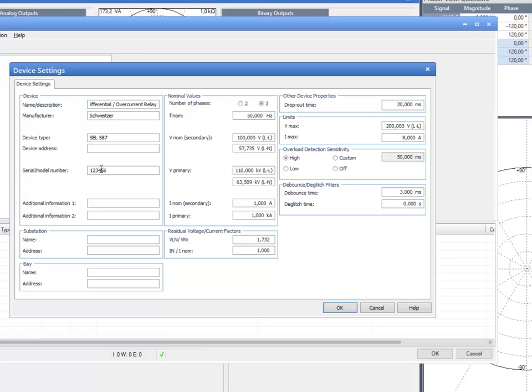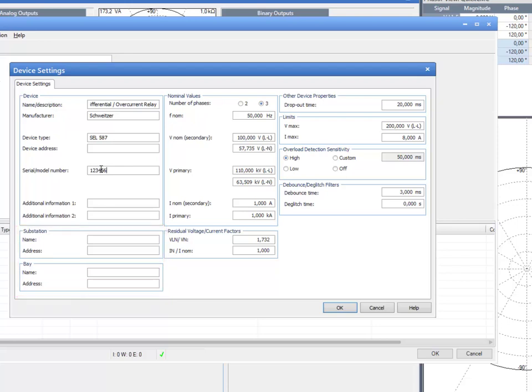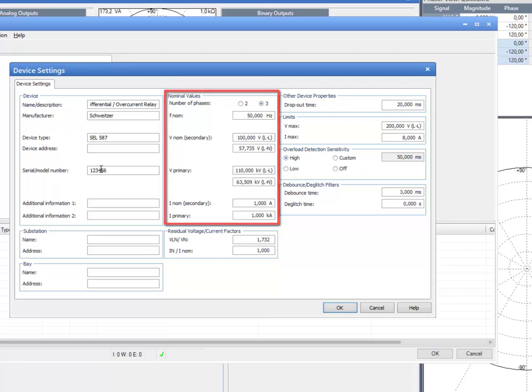Describe the location of the device in the substation and bay sections. In the section of the window, you can set the nominal values of your power system network, including primary and secondary values for voltage and current and the frequency of the network. The test modules will use these values for calculation.